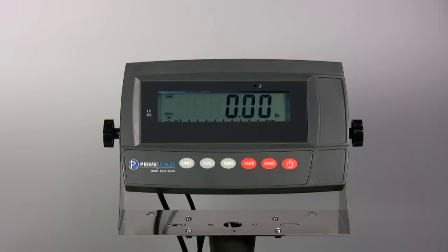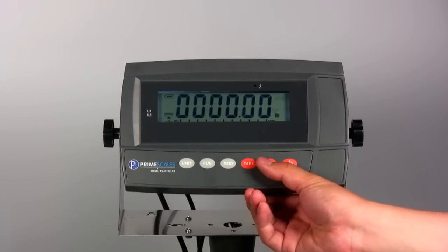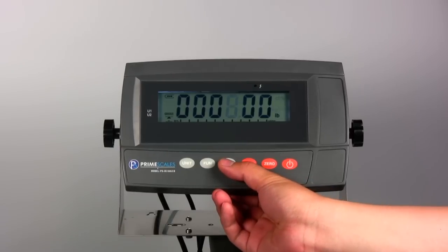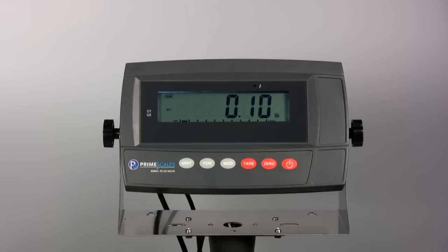Pre-tare function: If you want to tare off a known weight of the container, you can use this function. In the pre-tare mode, press MOD key to input the weight of the container, then press FUN key to confirm. Then the scale will display the net weight.